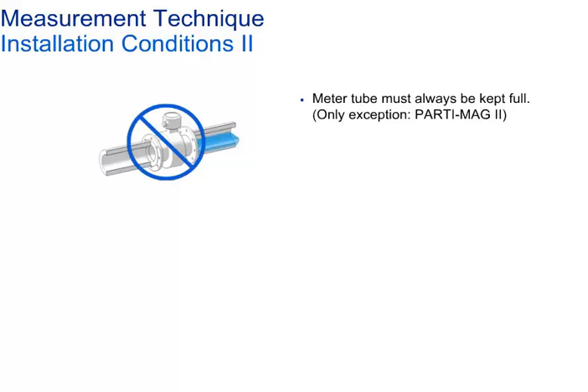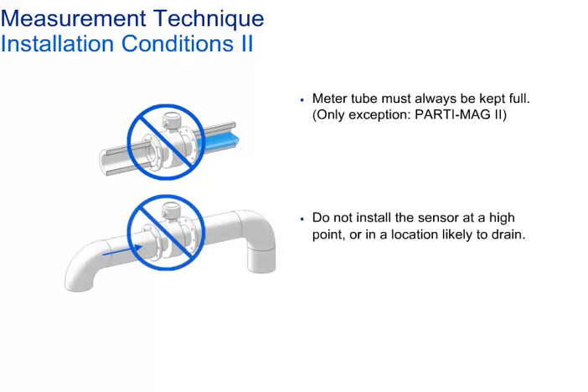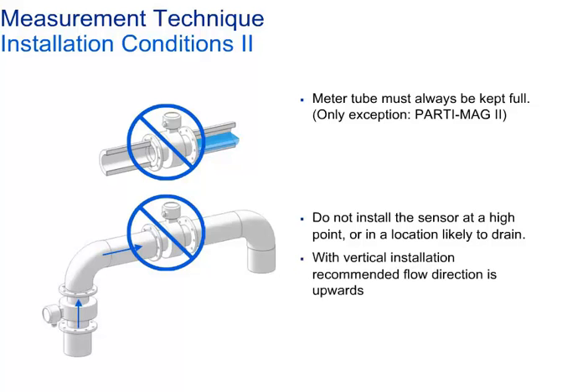Observe the following installation recommendations to ensure proper operation of your meter. The pipe needs to be kept full — the only exception is the ABB PartialMag model, which is designed for wastewater applications with partially filled pipes. Do not install the sensor at the highest point or on the draining-off side of the pipeline, as the sensor may run partially filled due to air at the highest point. With vertical installation, the recommended flow direction is upwards.